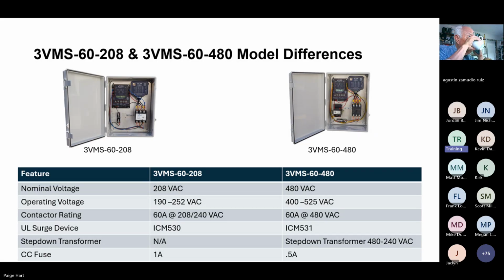And then, of course, the fuse, right? You're going to have a 1 amp fuse in the 208 version and a 0.5 amp fuse in the 480 volt version. What's nice about the step down transformer in the 480 volt version that's not mentioned here is that it has a little circuit breaker on it itself. So basically, if anything goes wrong, you've got a secondary backup for protection, where the little circuit breaker on the step down transformer will open if it sees a current beyond, I want to say it's 3.5 amps.